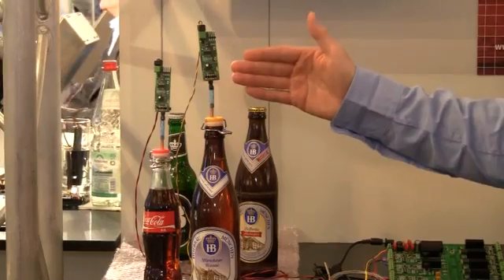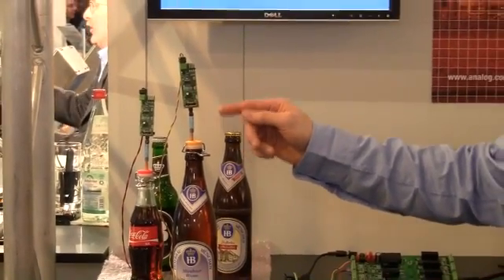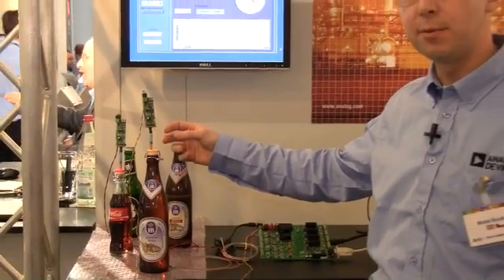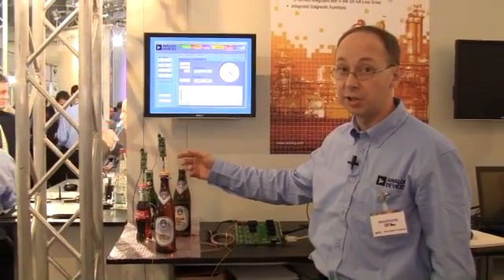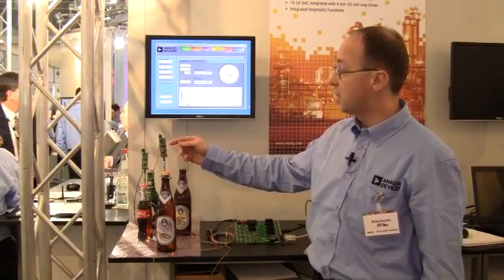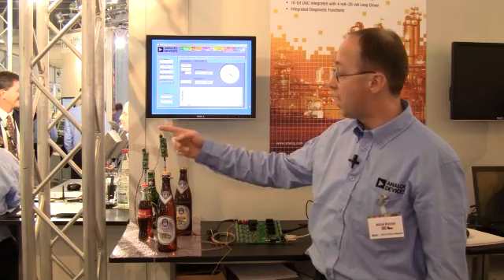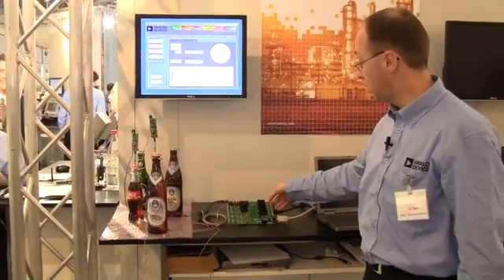This field instrument consists of two main components. One is an analog input signal processing chip that processes the signal from the pressure sensor, doing linearization, compensation, and calibration. The other chip sends the signal representing the pressure via a 4 to 20 milliamp standard industrial interface to a process control system.